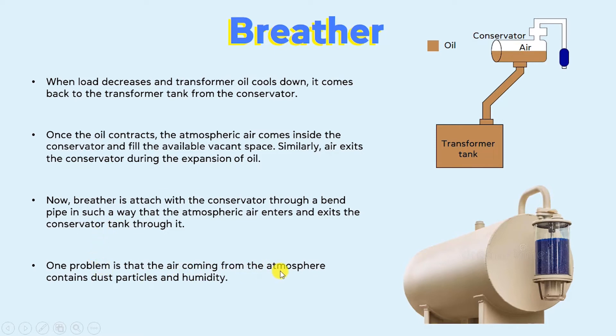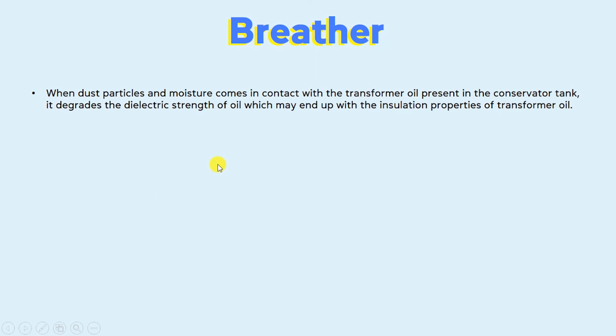One problem is that the air coming from the atmosphere contains dust particles and humidity. When the dust particles and moisture come in contact with the transformer oil present in the conservator tank, it degrades the dielectric strength of oil, which may affect the insulation properties of transformer oil, ultimately affecting the working of the transformer.